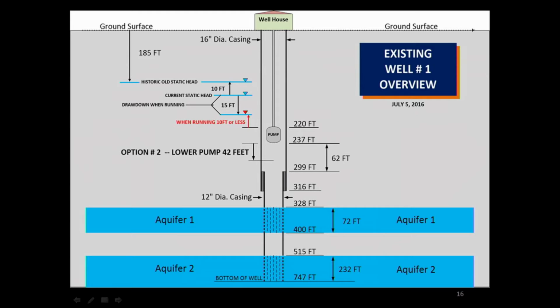At the surface we have an existing shaft casing of around 16 inches, which goes down about 299 feet, then necks down to a 12-inch casing that takes you into the two aquifers. The pump sits 220 feet below the surface. The historic static head, the resting water level, used to be around 185 feet, but now we're finding it about 10 feet lower than that. That's part of the problem — we don't have as much head as we used to. We're not sure what causes that, but that's what the guys have seen looking at the different SCADA reports.